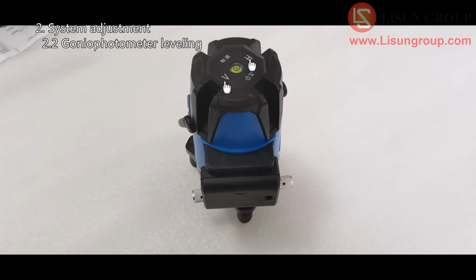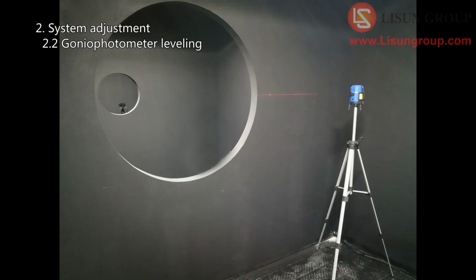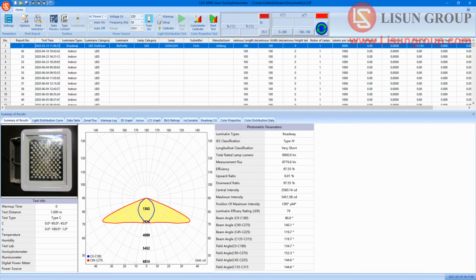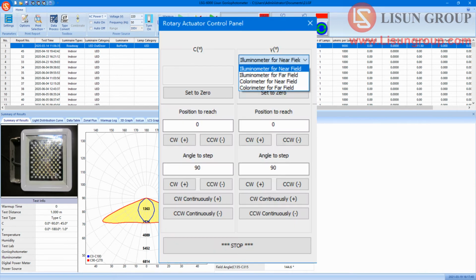There are the switches for the vertical laser and horizontal laser on the top of the device. Turn on the horizontal laser. Adjust the height of the laser to the height of the goniophotometer and the center height of the holes in the partitions. Open the software. Click Type Convert to show the C-gamma angle. Click Rotary Actuator Control Panel.